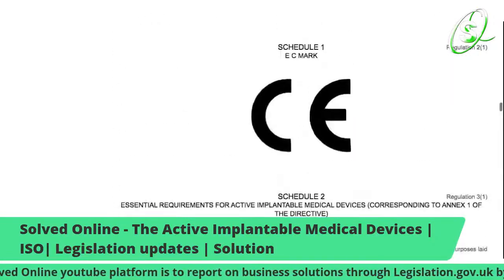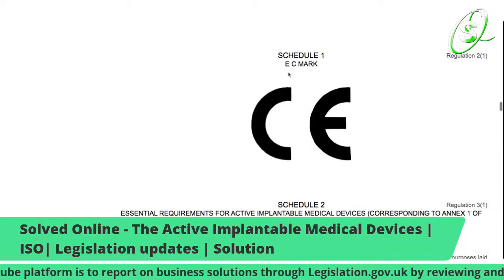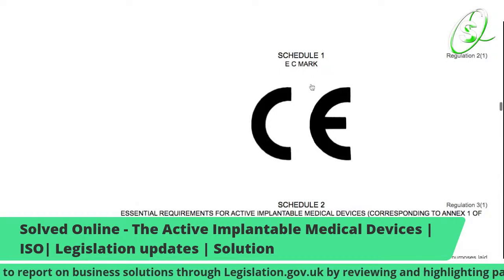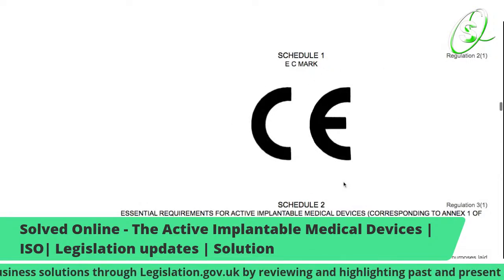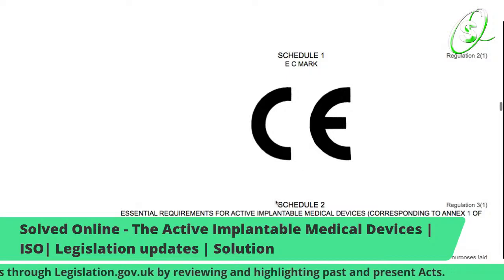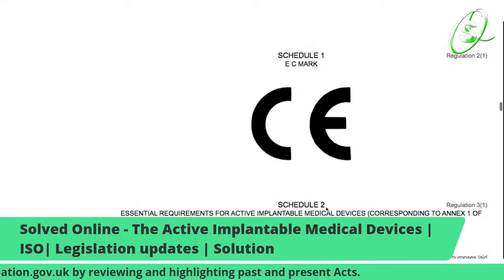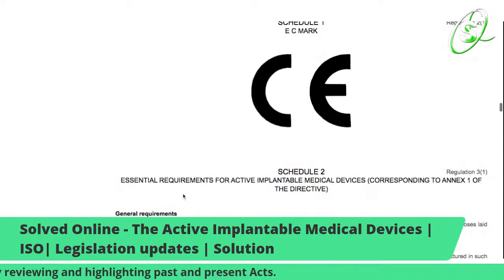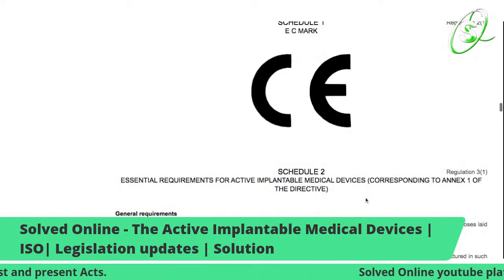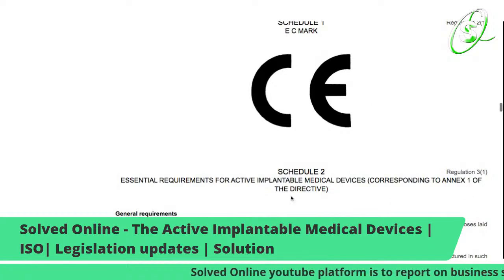And this is Schedule 1, and it has the EC mark, and this is the actual EC mark from what I just showed from the other slide. And this is Schedule 2. It shows you essential requirements for active implantable medical devices corresponding to Annex 1 of the directive.